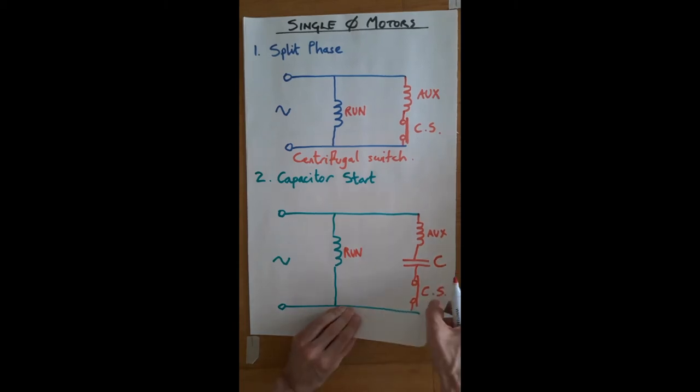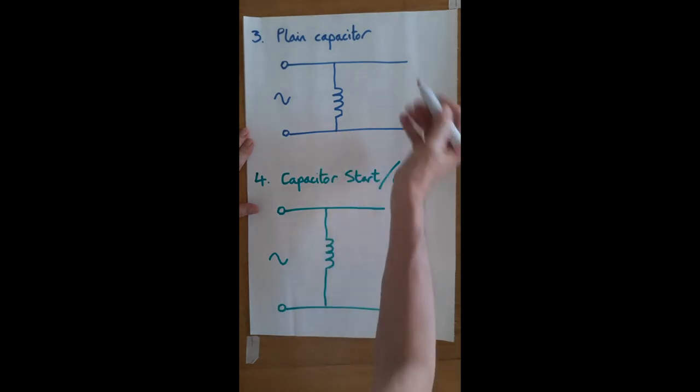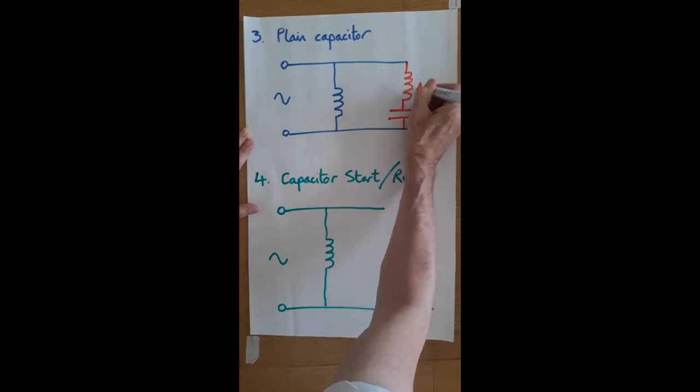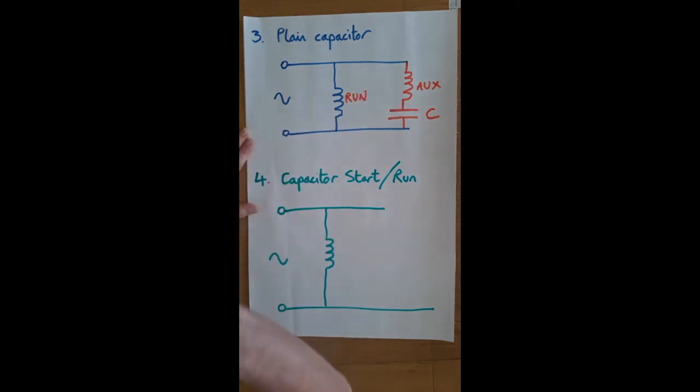The plain capacitor motor - I'm sure that many of you have seen these around. The plain capacitor motor has the auxiliary winding and it has a capacitor. So this is the auxiliary and this is capacitor, and this is the run winding. In this circuit, these are permanently left in circuit, they're not switched out. And this type of motor is very commonly used for central heating pumps, and that's probably the place where most of you will be likely to see it.